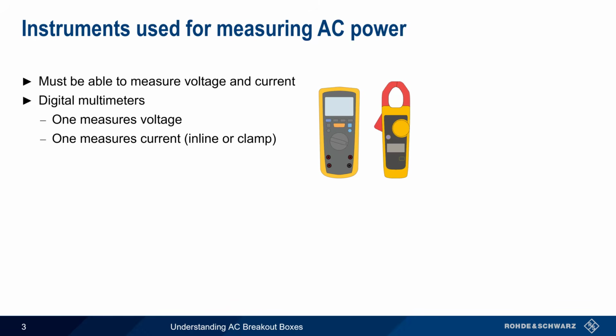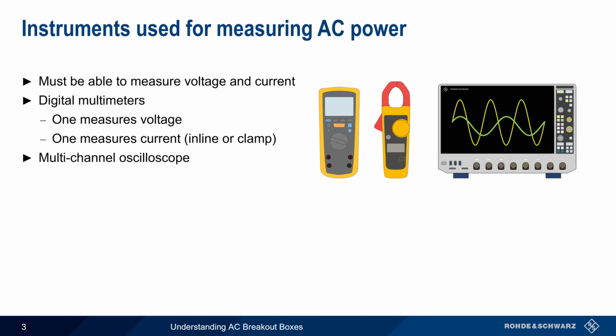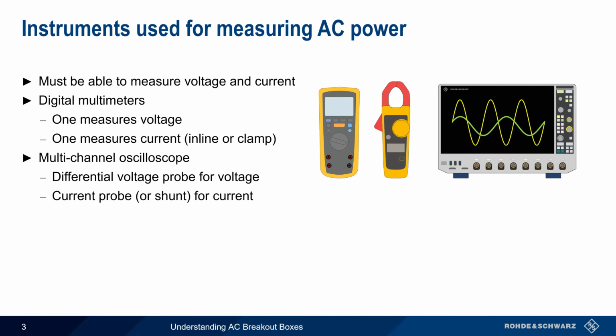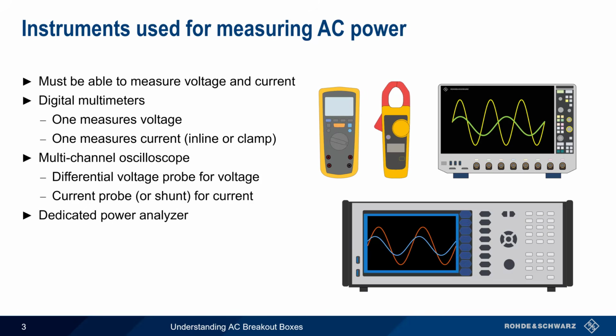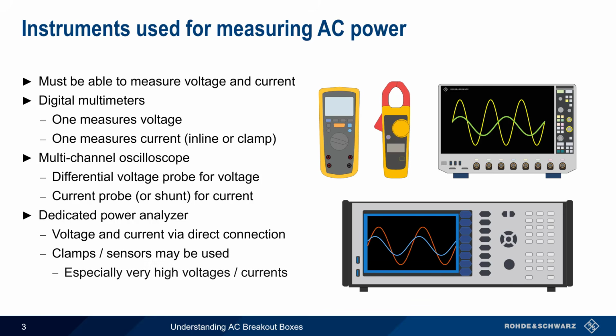A more convenient and more accurate way of measuring AC power is using an oscilloscope. Here, a differential voltage probe is used to measure the line to neutral voltage, and a current probe or shunt is used for measuring current. However, the easiest and most accurate method of measuring AC power is using a dedicated power analyzer. These provide direct banana jack connections for both voltage and current, although external clamps or sensors may be used when measuring very high voltages and currents.